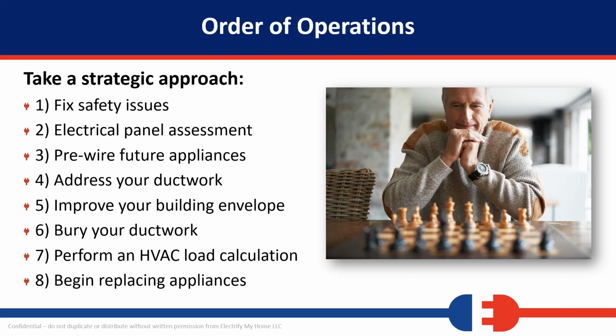Always insist that your contractor perform an HVAC load calculation. This is not going to be a preset form where a lot of numbers go in and then magically out the other end turns out whatever size they think you need. You should do a manual J and manual D load calculation on these at minimum, so you can determine room by room airflows and also what size system you actually need.